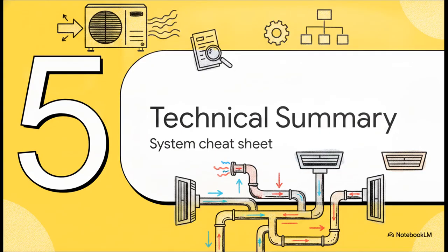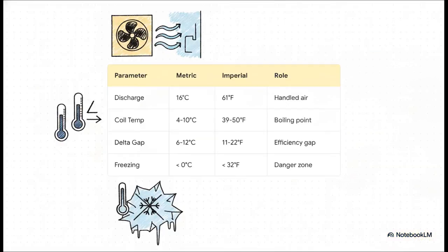Finally, part 5, a technical summary. This is your system cheat sheet. Pulling all of this together, you've got your discharge air at 16 degrees handling the room, and your typical coil temperature resting roughly 6 to 10 degrees below that at its active boiling point. That delta between the air and the coil is your actual efficiency gap. And the very moment you cross that 0-degree freezing threshold, you are completely in the danger zone for coil icing.